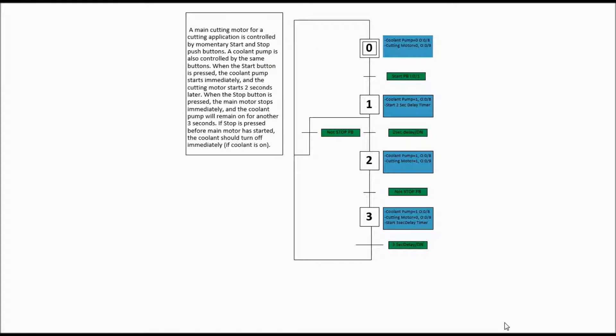Let's go over the tasks again before we start writing the logic, just so we remember what we were doing last time. A main cutting motor for a cutting application is controlled by momentary start and stop push buttons. A coolant pump is also controlled by the same buttons. When the start button is pressed, the coolant pump starts immediately, and the cutting motor starts 2 seconds after. When the stop button is pressed, the main motor stops immediately, and the coolant pump will remain on for another 3 seconds. If stop is pressed before the main motor has started, the coolant should turn off immediately.